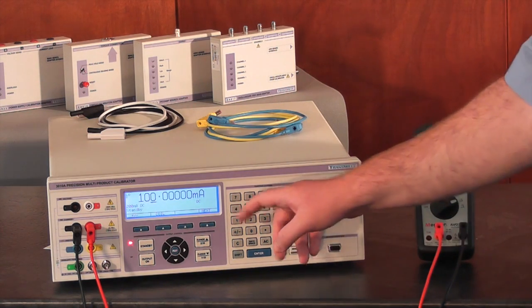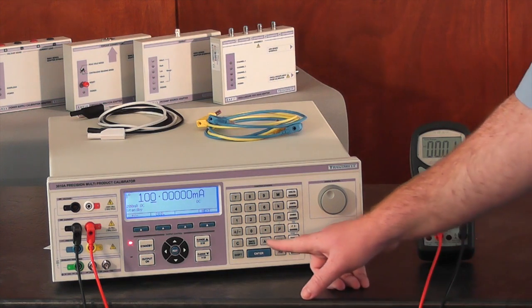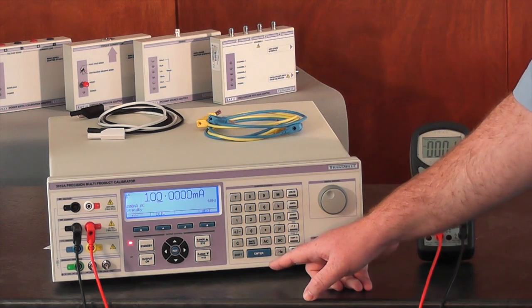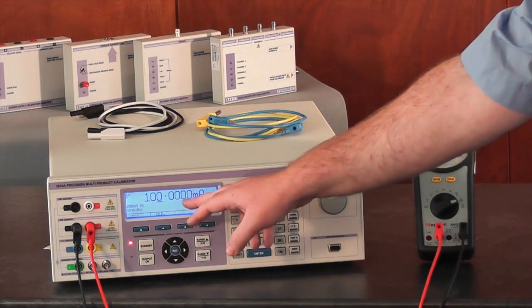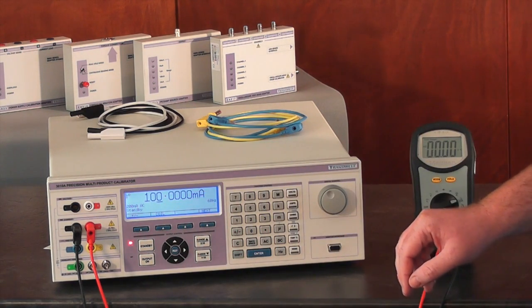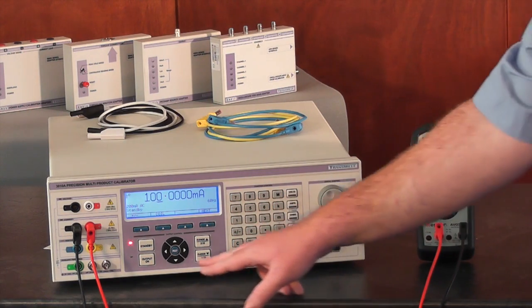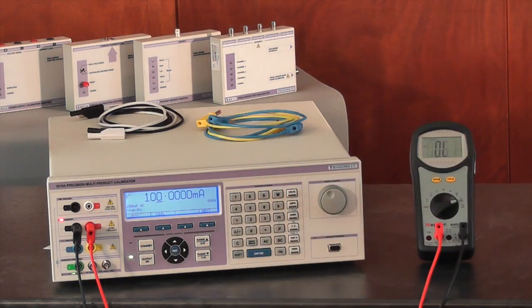To switch the 3000 series calibrator into AC mode, simply press the AC key. The last value is carried across. We already have a setting of 100 milliamps. We will be testing at 60 hertz, so we press the output on and verify the measurement on the multimeter.